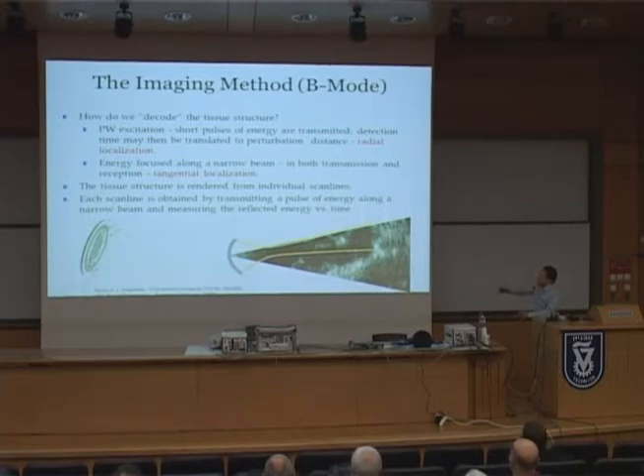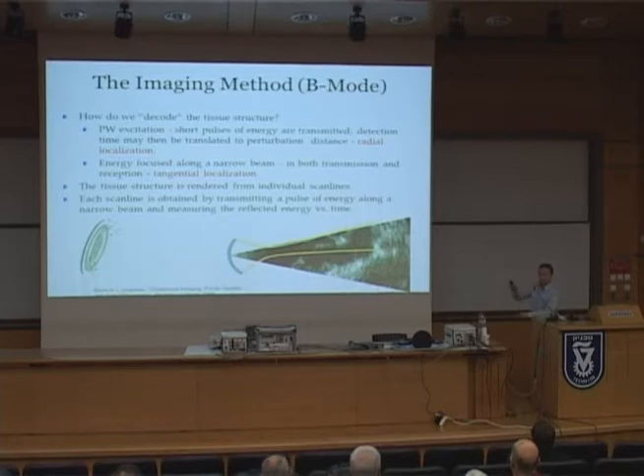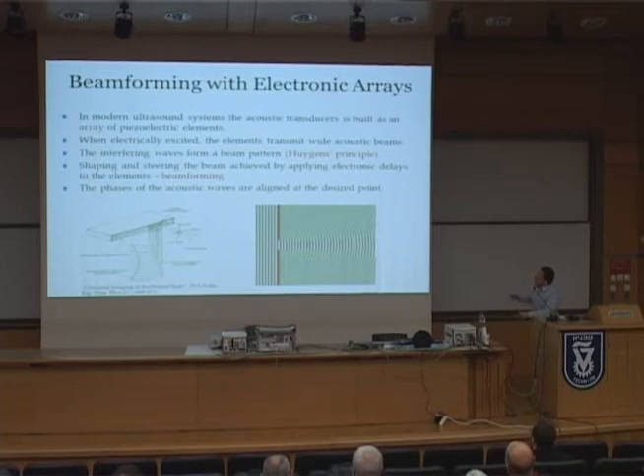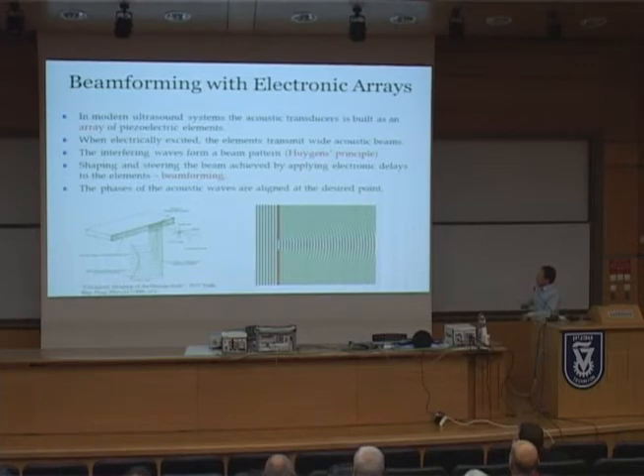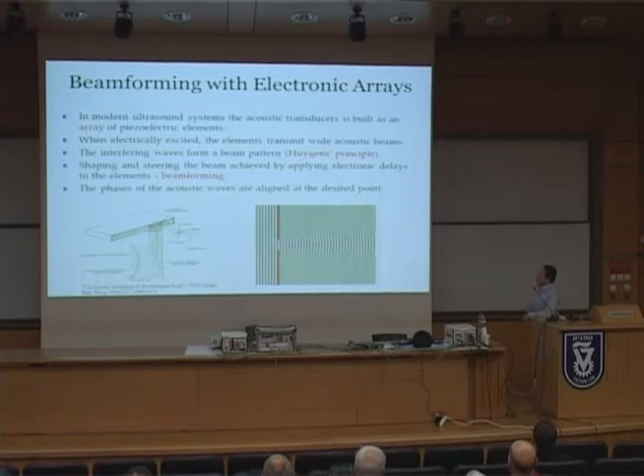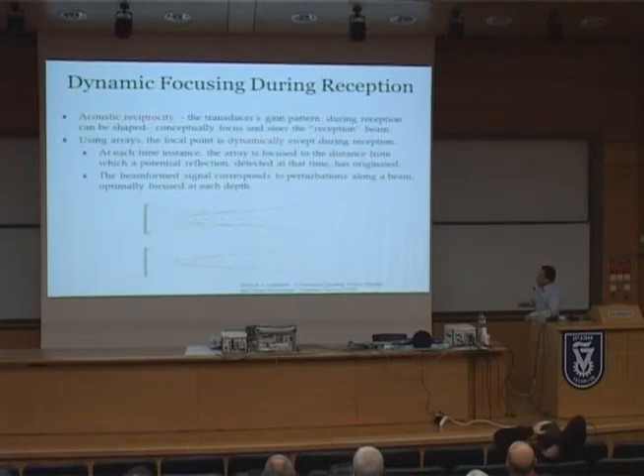Focusing of energy is done by mechanically shaping the transducer as a curvature as part of a spherical shell, with the center of curvature serving as the focal point. Modern ultrasound systems utilize electronic arrays where the transducer is built as an array of piezoelectric elements. Each small element transmits a wide acoustic beam when excited, and these interfering beams form a typical beam pattern by Huygens' principle. The shaping and steering of the beam can be achieved by applying electronic delays to the transmitting and receiving elements — for instance, aligning phases at a desired focal point. This focusing concept also applies during reception by exploiting acoustic reciprocity theory.